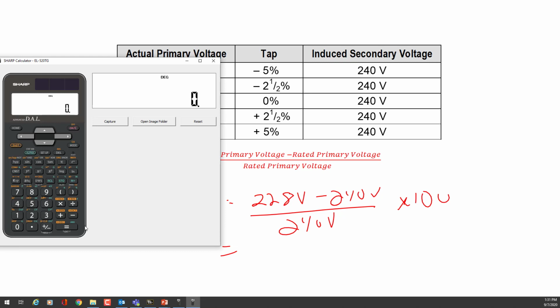So clear. 228 minus 240 equals minus 12. Divide by 240. 5% tap negative, so times 100. So we can do it with the secondary voltages too. That means that I have to go to the primary and adjust it to the minus 5% tap if I only had 228 volts on the secondary. Anyways, so that's kind of how that works.